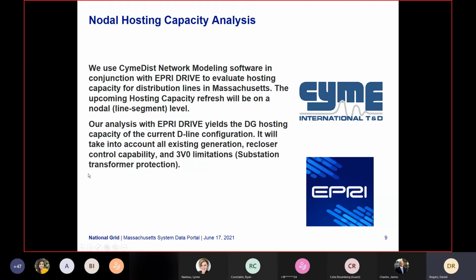The analysis afterward will include some post-processing. So we will include a flicker analysis, as well as a 3v0 limitation screen. So this will take into account all the existing DG on that substation transformer bank, and then base it against minimum load, and then it'll give a threshold for what may or may not trigger 3v0 to be needed in areas that need it. The areas that don't need it are marked on the map in the substation information.